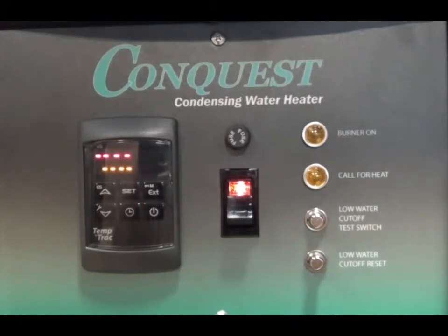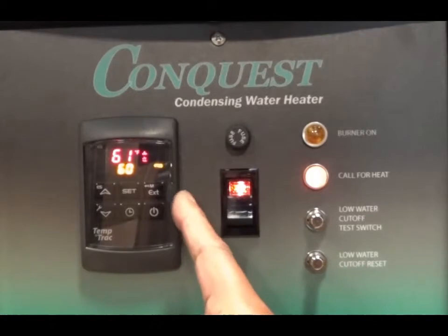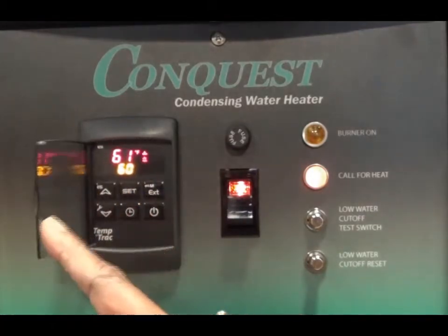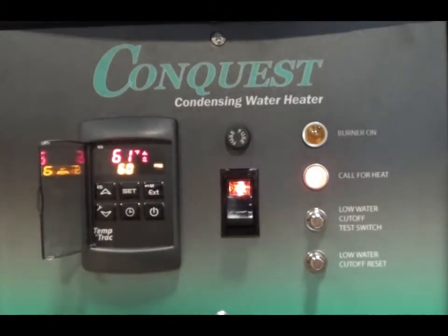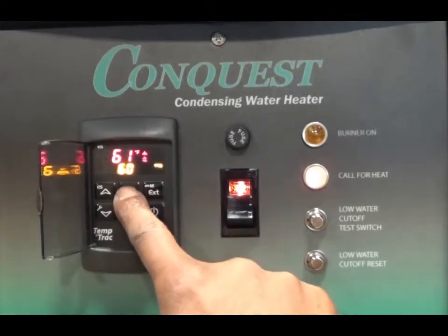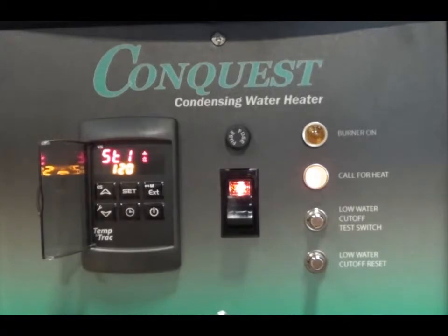A small flame icon and the call for heat light immediately illuminate to indicate that the call for heat sequence is initiated. The display screen also shows a flashing Valve M icon to indicate that the control's digital input terminals 18 and 21 are activated and waiting for a signal to confirm the gas valve is energized and flame is proven. To display the Temptrac control set point, press and release the set button. The factory set point of 120 degrees is displayed. Press the set then up buttons together to return to the home screen.